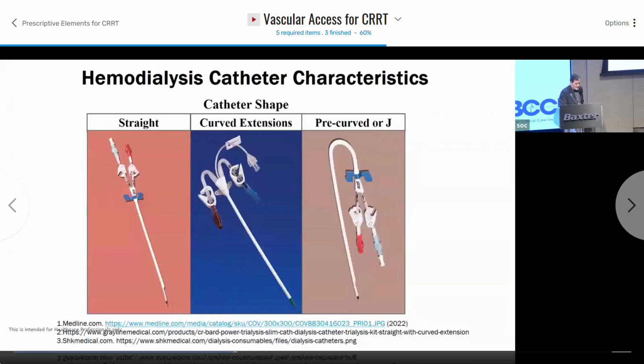But the other characteristic is what the shape of the catheter is. In theory, based off of Poiseuille's, straight would be better. But as everybody knows, straight up in the neck oftentimes is never straight because things are curving around and you're moving it and everything. And so that's problematic. These curved extensions were meant to help with that in a way, but you have to be careful because they can kink up in these curves right there. And again, I'm introducing another curve, which I'm losing my laminar flow during, and so it's a problem. This, I do lose some of the laminar flow because of the pre-curve, but because it's a rigid catheter, you don't have deformation of it.